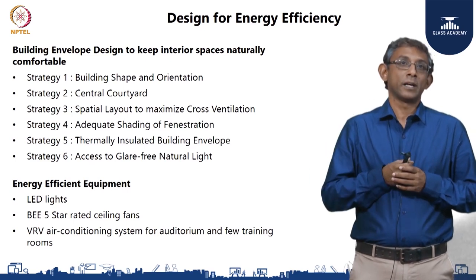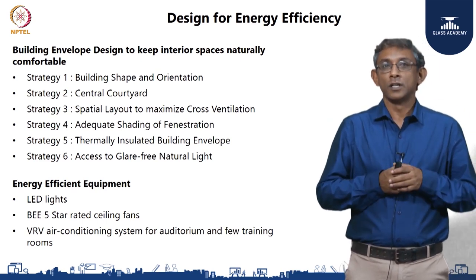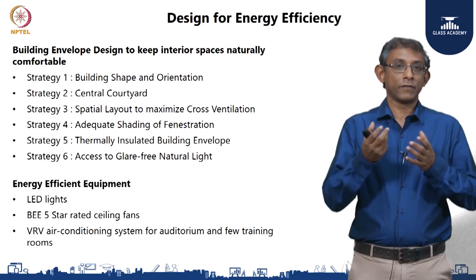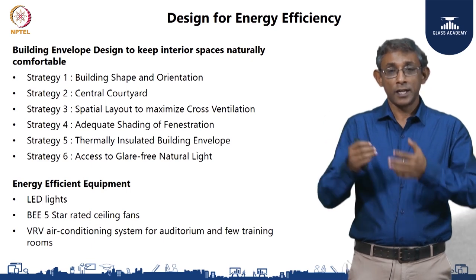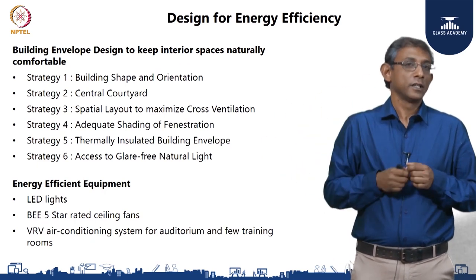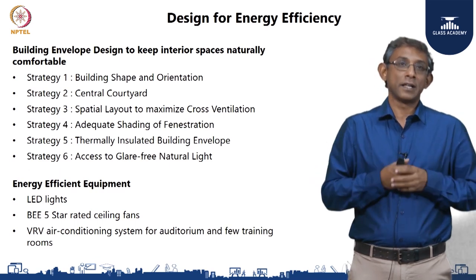To summarize, in terms of designing an energy efficient building we looked at two things: passive measures built into the building itself, and active systems. For the passive measures — strategy one was the building shape and orientation: the round shape with minimal exposure to the west and breezeways through the south, the prevailing wind direction. Strategy two was the central courtyard which allows a stack effect and aids cross ventilation. Strategy three was ensuring all regularly occupied spaces have openings in at least two orientations — every space had an opening into the courtyard as well as into the exterior environment — ensuring movement of breeze from one side of the building to the other. Strategy four was adequate shading of the fenestration, achieved by slab overhangs and the roof overhang, which also created usable balcony and walkway spaces.